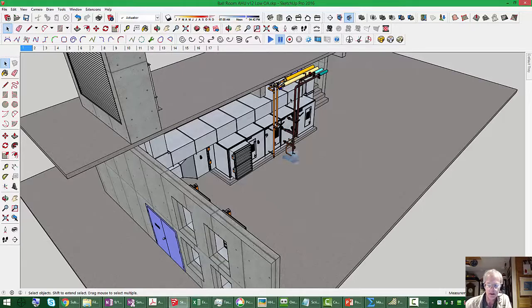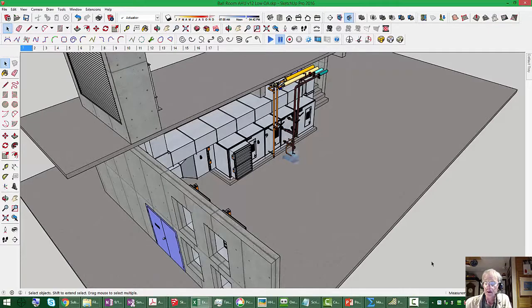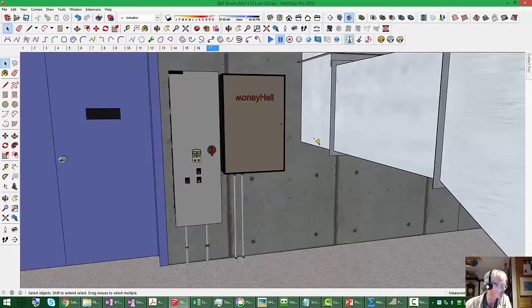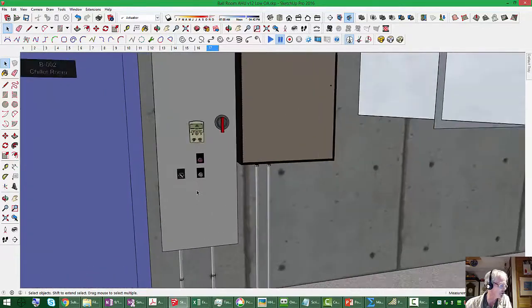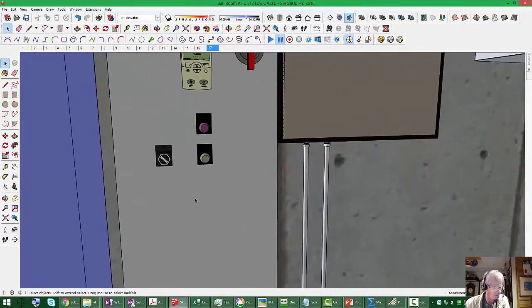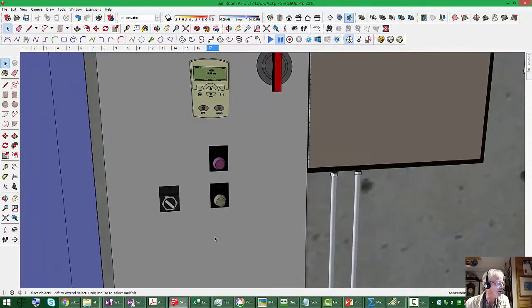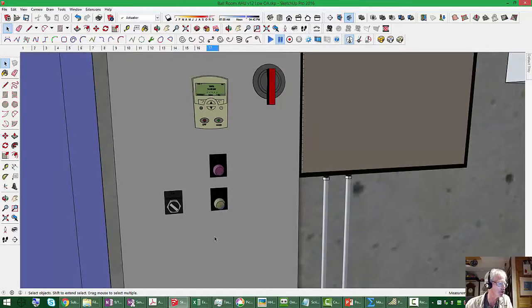In looking around the mechanical room, depending exactly on what you looked at, you might have actually been tempted to think it's a variable volume system, because there's what appears to be a variable speed drive. And that wouldn't be a bad assumption, but to know it for sure, you'd have to know a little bit about the system. You'd have to know what the terminal control equipment's like.